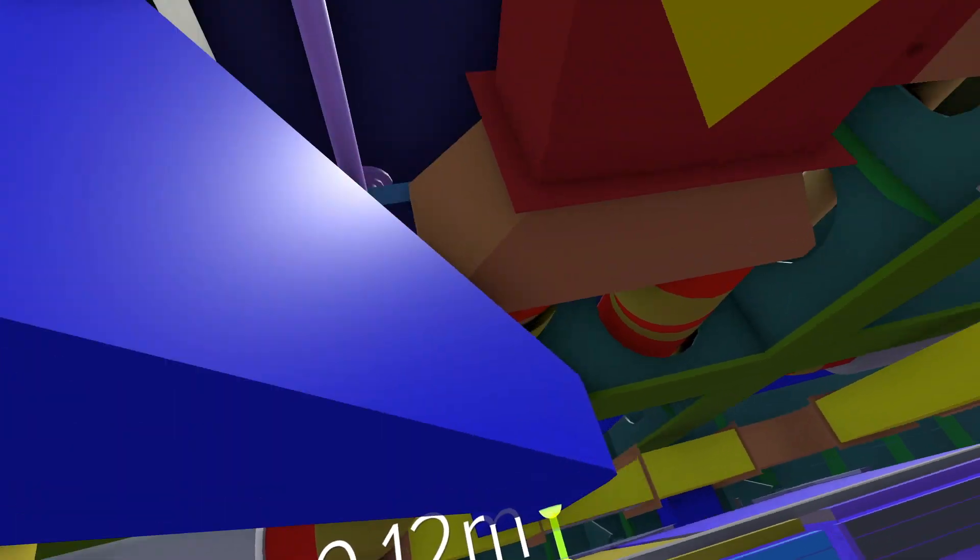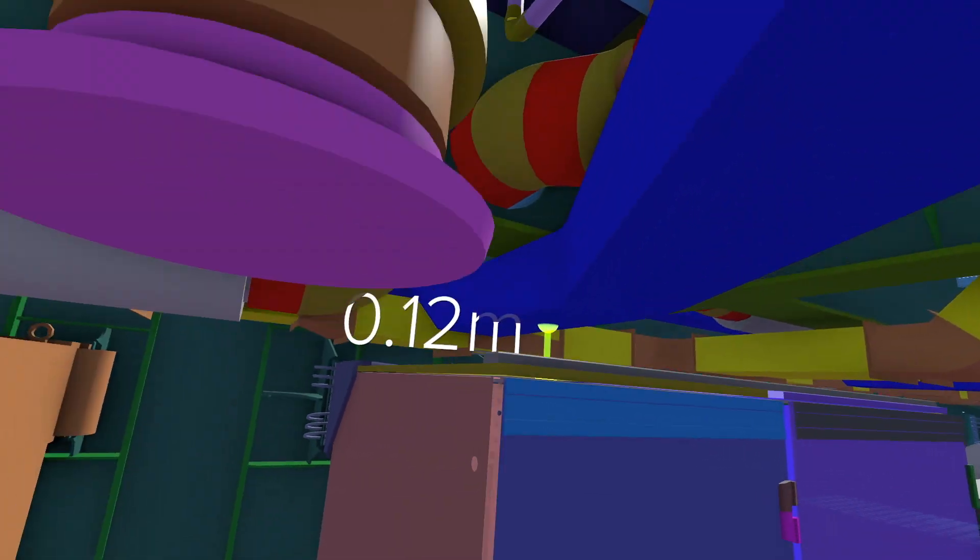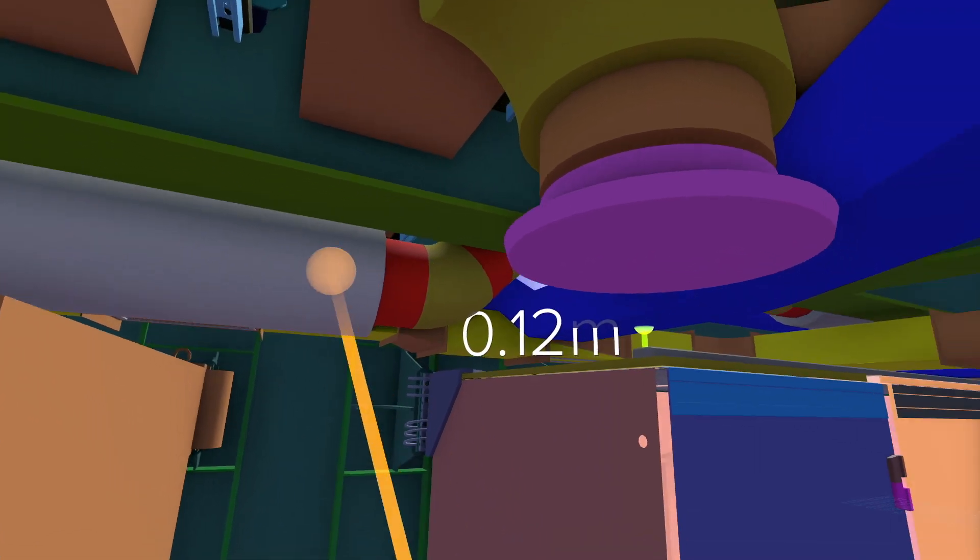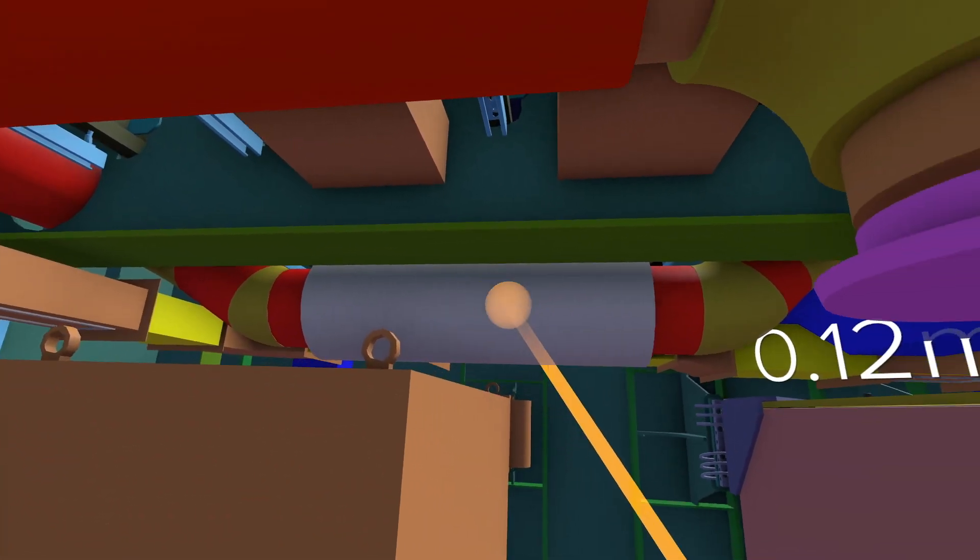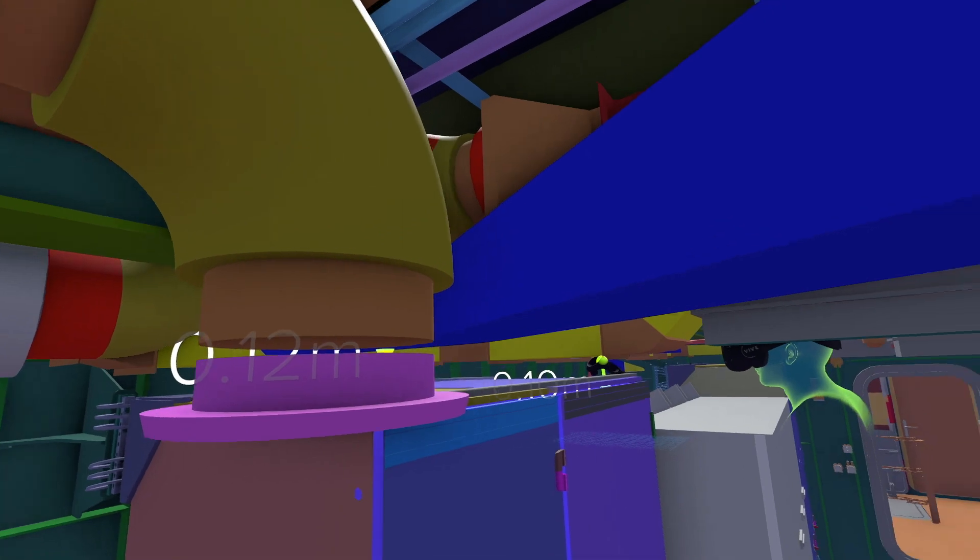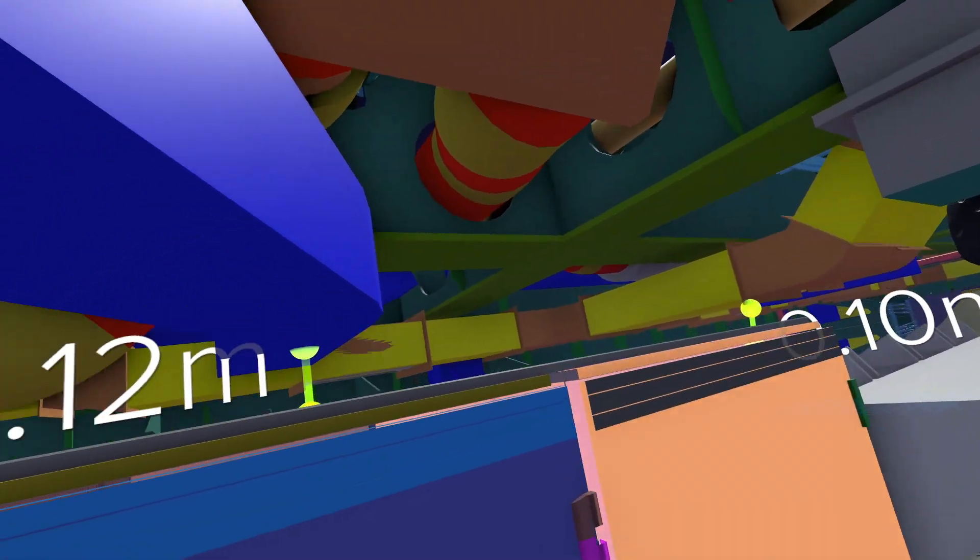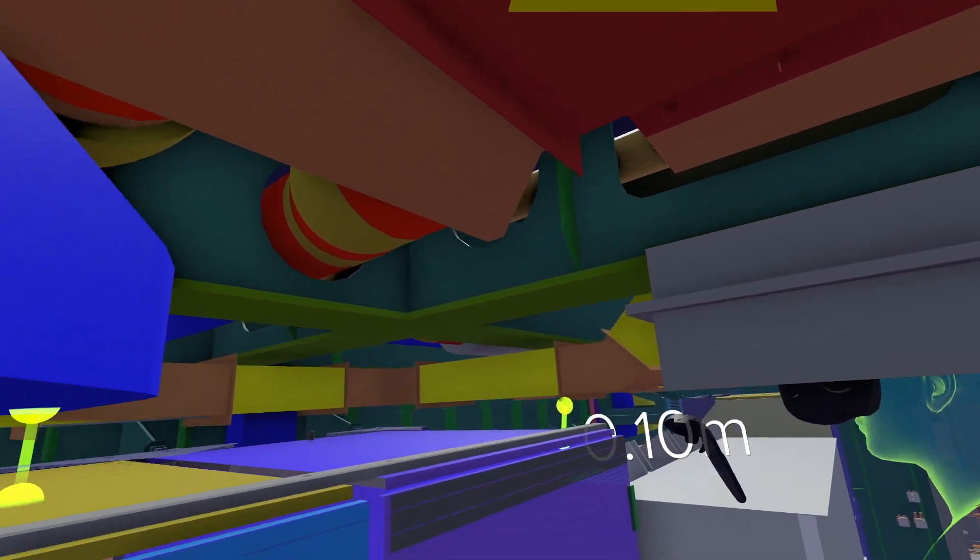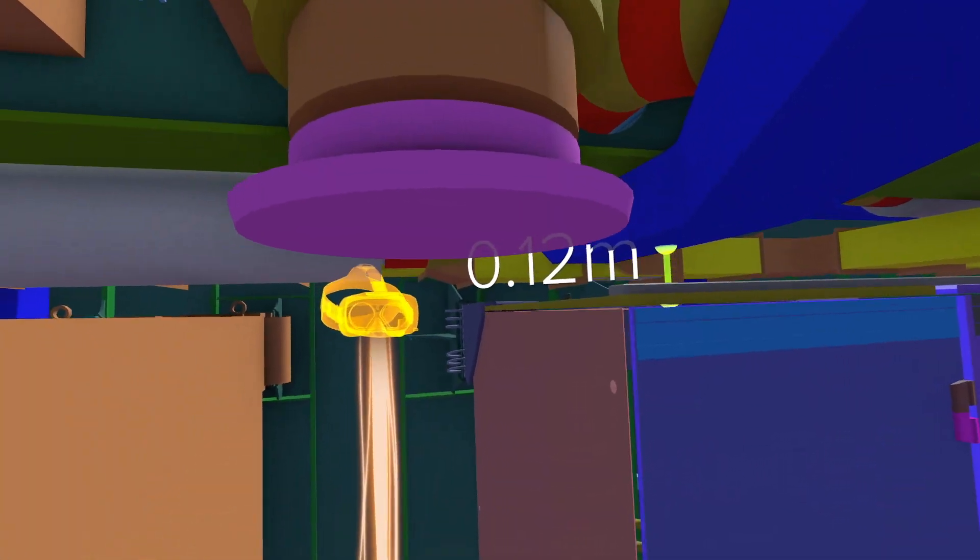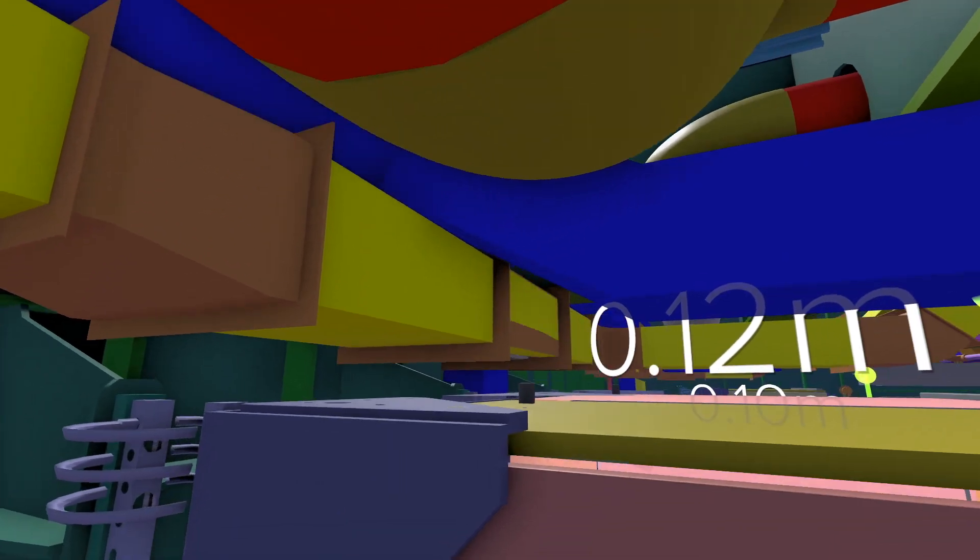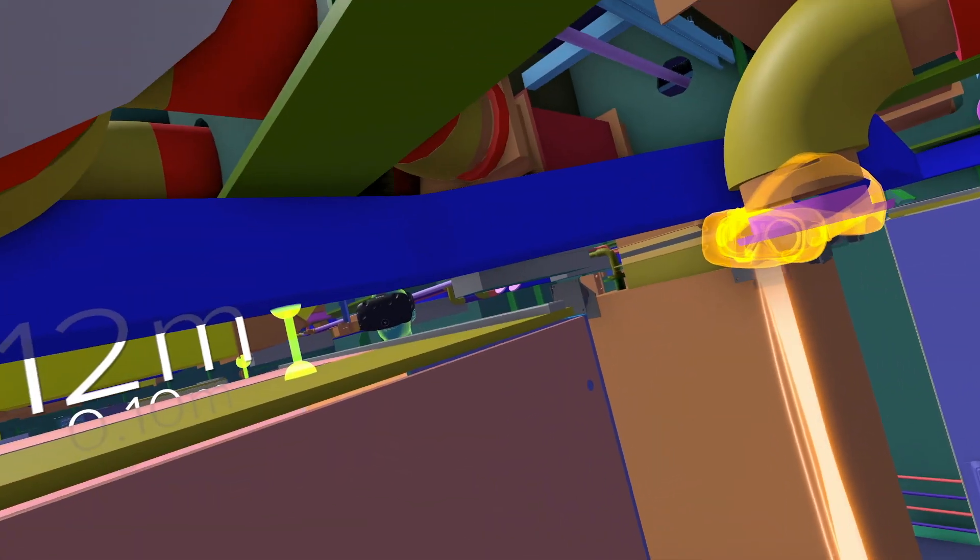Right. Okay. Well, are we able to move this cable tray across? There's this silencer in the way here. I'd have to check the noise counts to see whether we could make it shorter. Okay. Well, we can get away with that, I reckon. But this HVAC with the flanges is definitely going to be an issue. That's going to clash. As well as the duct back here. It's the same thing.